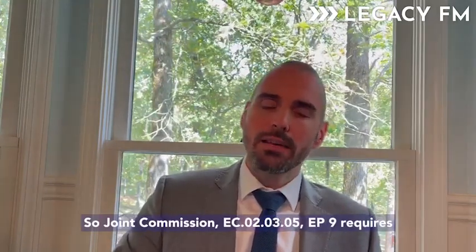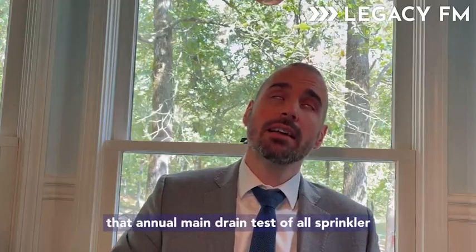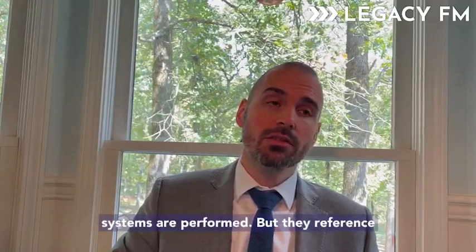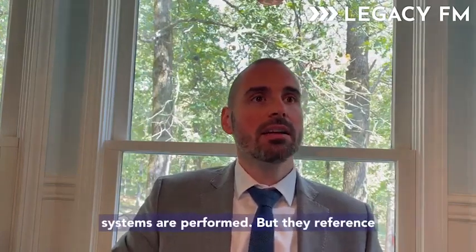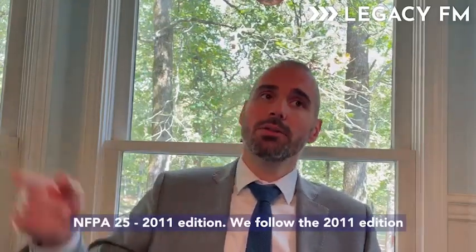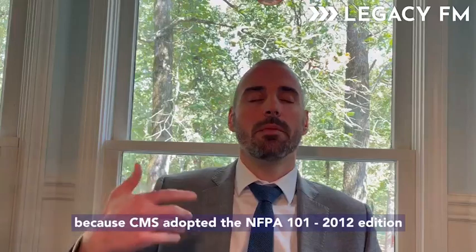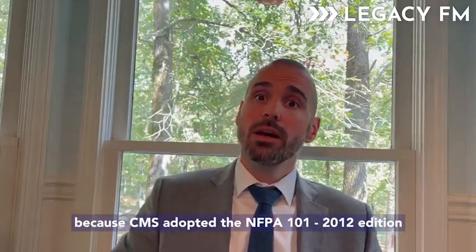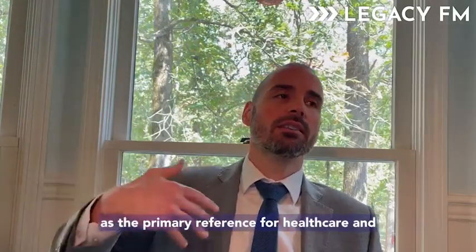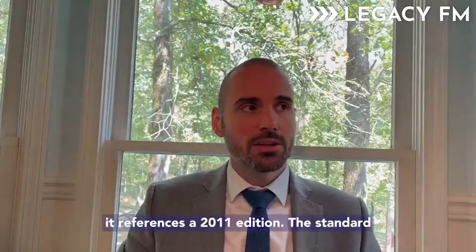So Joint Commission EC 02.03.05 EP9 requires that annual main drain tests of all sprinkler systems are performed. But they reference the NFPA 25, 2011 edition. We follow the 2011 edition because CMS adopted the NFPA 101 2012 edition as the primary reference for healthcare, and it references the 2011 edition.